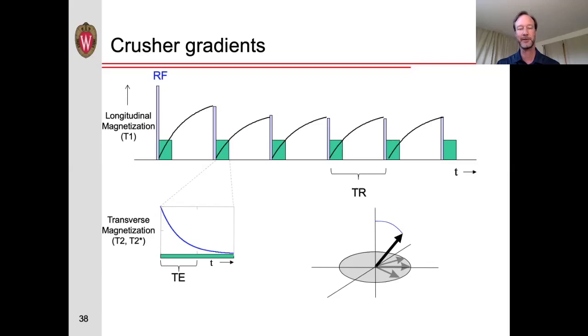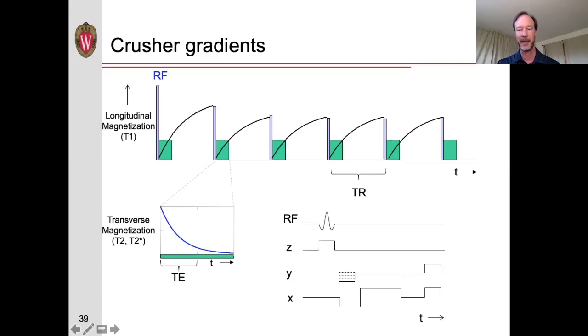And so one way to deal with this additional signal is to apply what are called crusher gradients. That is, after we've acquired our data, we apply additional gradients at the end of the sequence to remove any transverse magnetization. Then we can go on with our typical imaging. You'll also see that these crusher gradients play a role when we're doing certain kinds of preparation pulses.